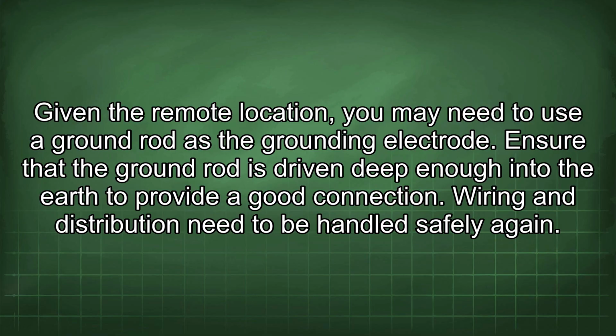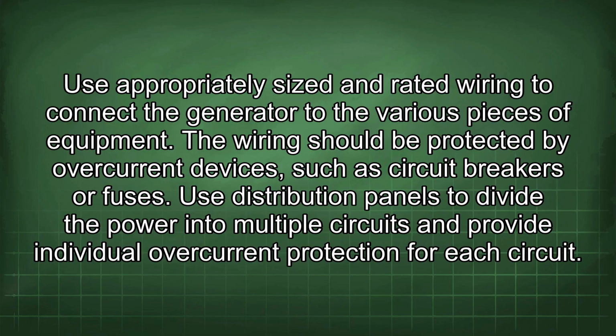Wiring and distribution need to be handled safely again. Use appropriately sized and rated wiring to connect the generator to the various pieces of equipment. The wiring should be protected by overcurrent devices, such as circuit breakers or fuses. Use distribution panels to divide the power into multiple circuits and provide individual overcurrent protection for each circuit.